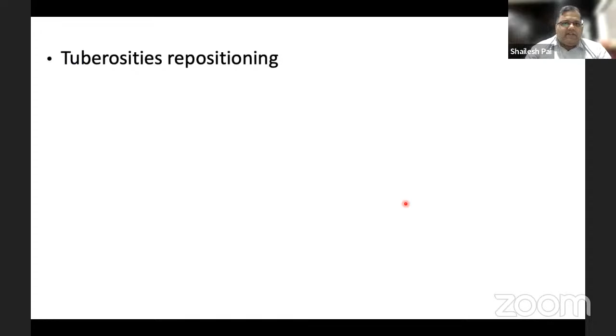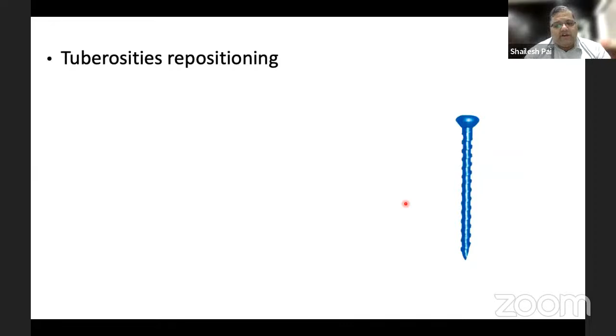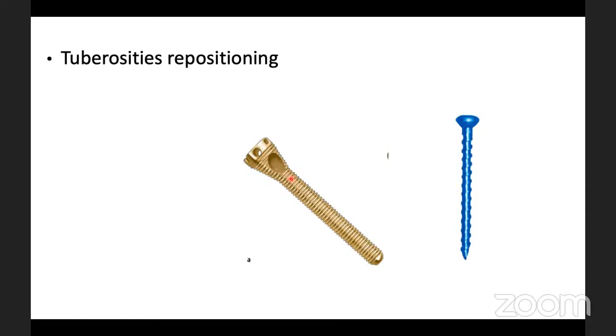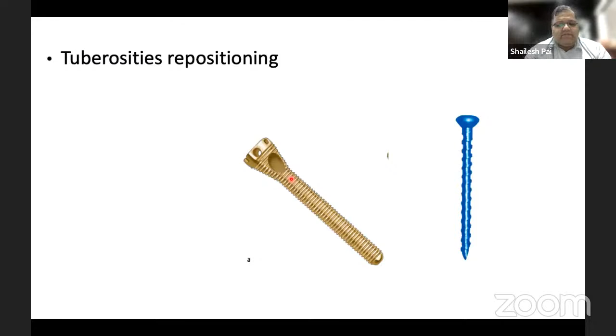Plus the previous generation nail had this bolt, which was again an issue because many times when we are inserting this bolt or screw, the tuberosity tends to splinter. We all know the tuberosity is a very, very flimsy bone, and intraoperatively splintering chances were high. Now in the current generation design of the bolt, we can see the undersurface is tapered, so it acts more or less like a washer. So the surface area is increased and hence the pressures are decreased, and hence intraop splintering does not happen.